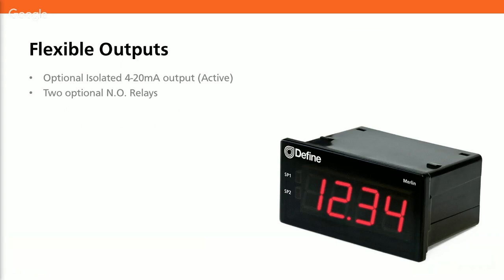It's also available with two normally open relays. The relays have multiple operating modes and can be configured independently from each other or set up into special linked modes such as pump alternation control mode. We're going to have a look at this mode and some of the other modes later on in the presentation.